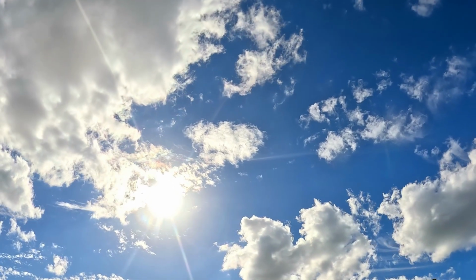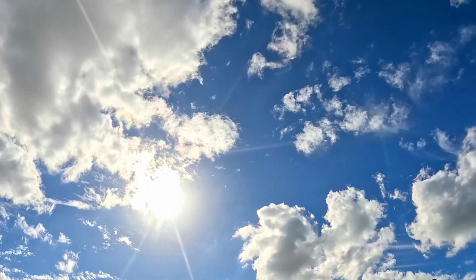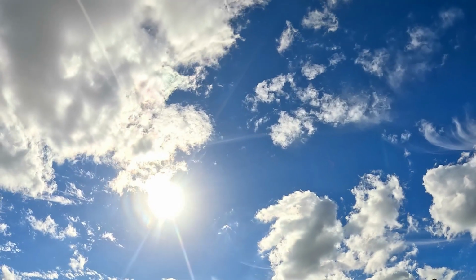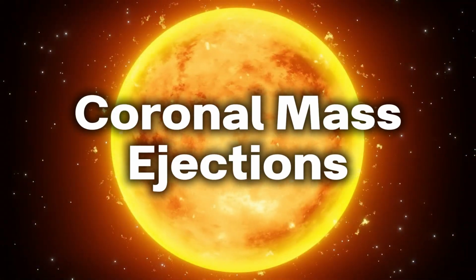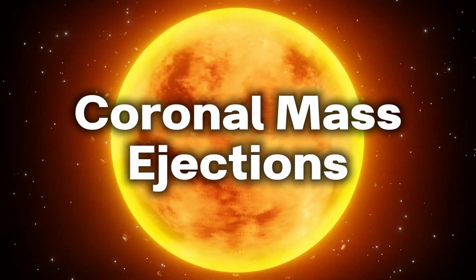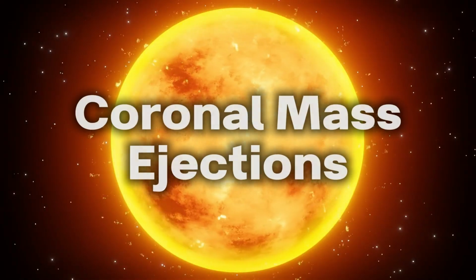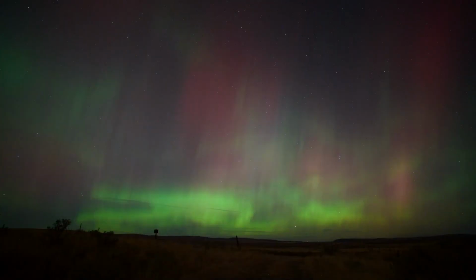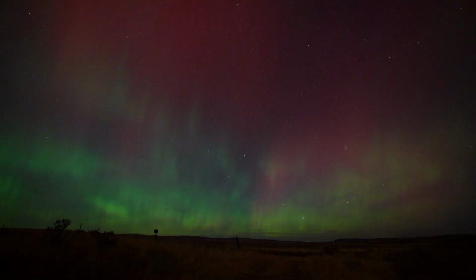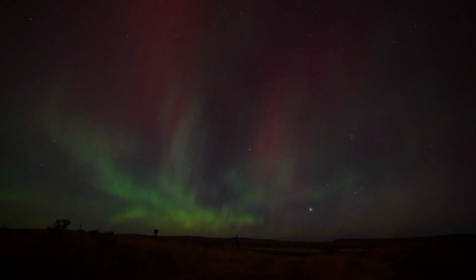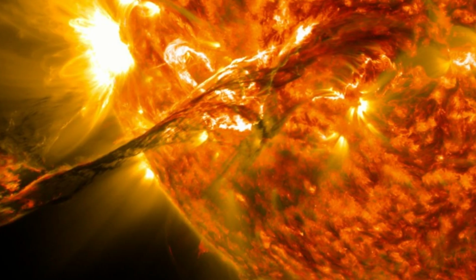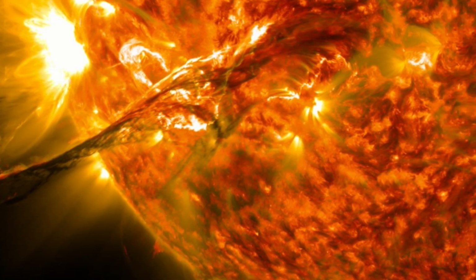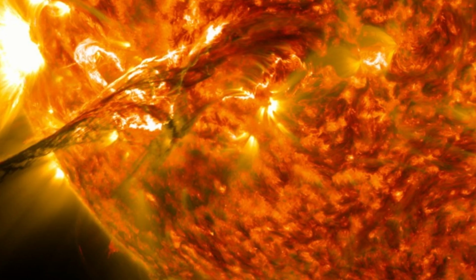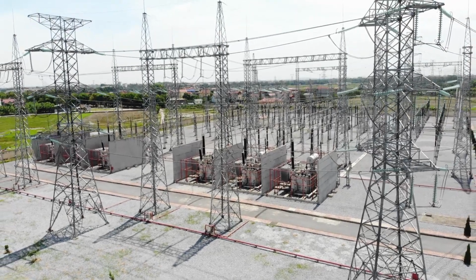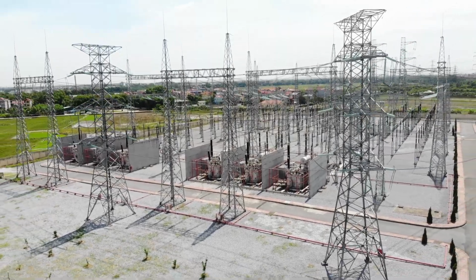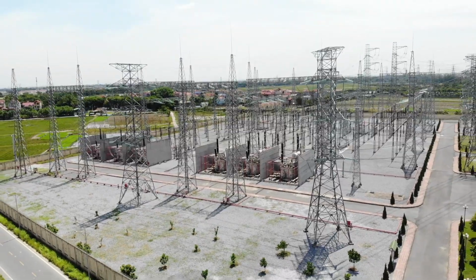One of the most serious risks to the grid doesn't come from Earth at all. It comes from space, from our sun. Occasionally, the sun releases enormous bursts of energy called coronal mass ejections. When these charged particles hit Earth's magnetic field, they can induce powerful electrical currents in long transmission lines. This phenomenon is known as a geomagnetic disturbance. The most famous example occurred in 1859 during the Carrington event. If a storm of that magnitude struck today, it could damage the extra high-voltage transformers that sit at the heart of our grid. These transformers are enormous and can weigh hundreds of tons. Many are custom-built, with replacement times measured in months or even years.